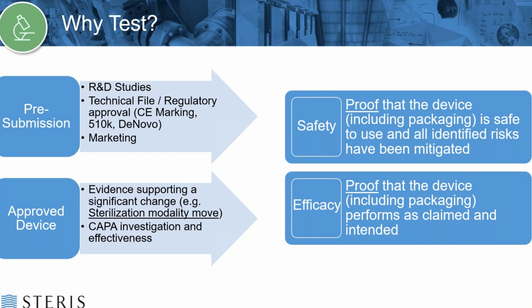So the purpose of testing is to prove the safety and efficacy of your device. So safety being the proof that the device, including the packaging, is safe to use and that all identified risks have been mitigated. And efficacy meaning the proof that the device, again, including the packaging, performs as it claimed and intended.